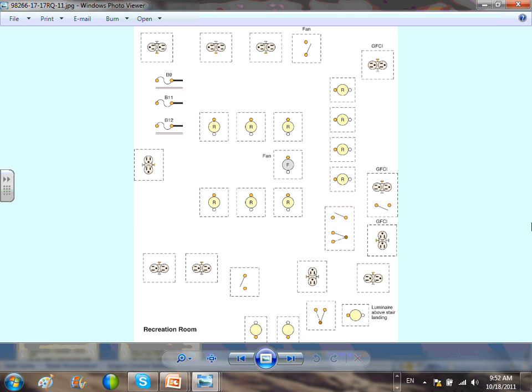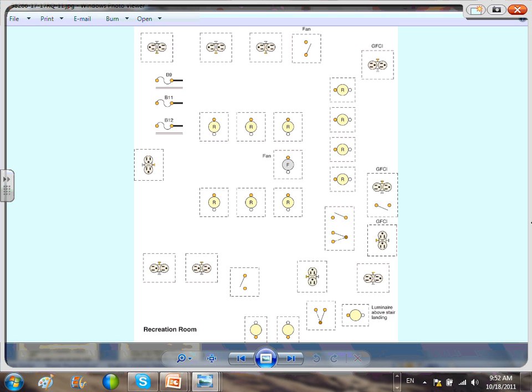Okay, the last thing I want you guys to do, when you have a chance, is please wire this one point-to-point. Point-to-point wiring. The most important things to remember when you do point-to-point wiring: every receptacle has to have a hot and a neutral. Every switch has to have a neutral, a hot, and a switched leg. 3 conductors. Three-way switches, you have to have a traveler, a neutral, and a switched leg or a hot, 4 conductors. If you have a 4-way switch, like we talked about, you need 5 conductors to make the system work coming to the 4-way switch. 4 travelers in, out, 1 neutral, and that's it.